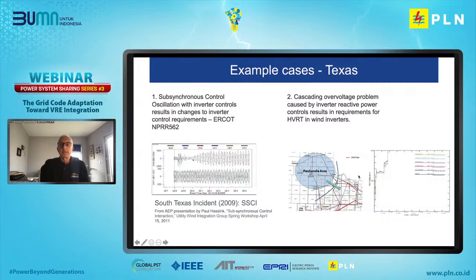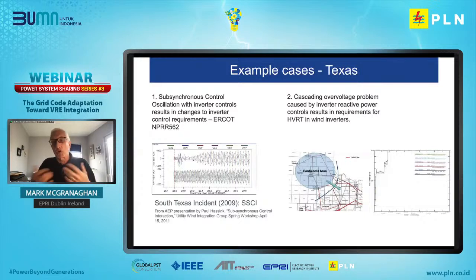On the right is an example of an overvoltage problem that occurred with wind generation in Texas. It was related to one of the requirements Roland described, that wind turbines provide reactive power to support voltage during fault events and prevent the system from going unstable due to low voltage conditions. This resulted in overvoltage when the fault was cleared, because of all the reactive power being fed into the system, causing wind turbines to trip on overvoltage and creating more problems. That led to new requirements for high voltage ride-through, and it was actually implemented as low voltage ride-through requirements as well in Texas.